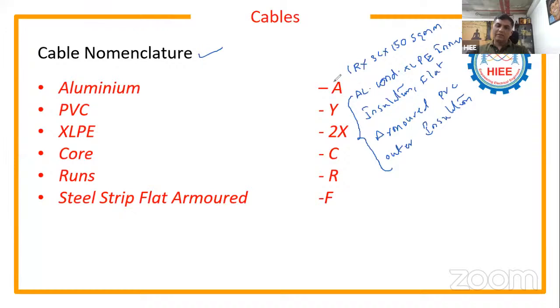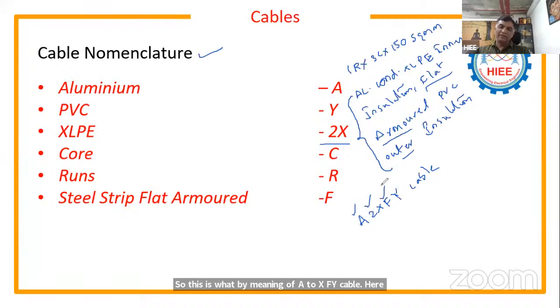So aluminum conductor is represented with A. Aluminum conductor with XLPE inner insulation: on top of aluminum conductor, XLPE is represented with 2X. And after that, your armoring is a flat armoring, represented with F, flat armored. And on top of armoring, the PVC outer insulation will be Y. So this is the meaning of A2X FY cable. A stands for aluminum conductor, 2X stands for XLPE inner insulation, F stands for flat armored, and Y stands for PVC outer insulation.